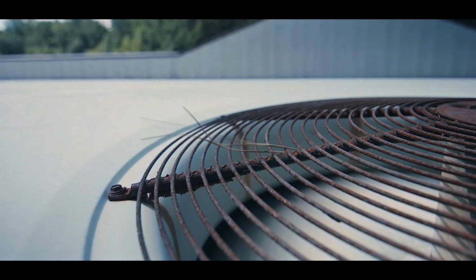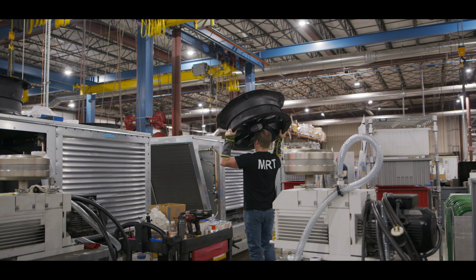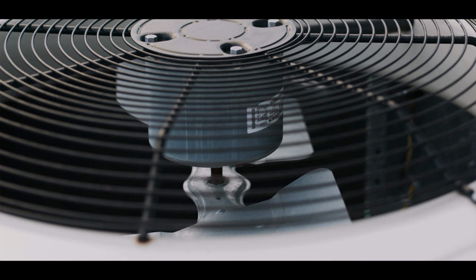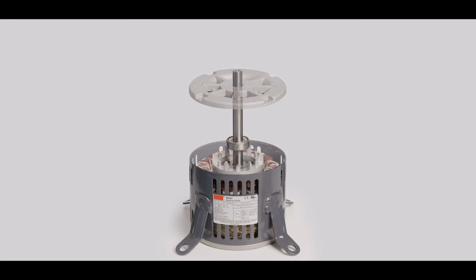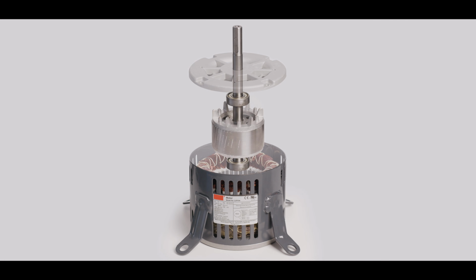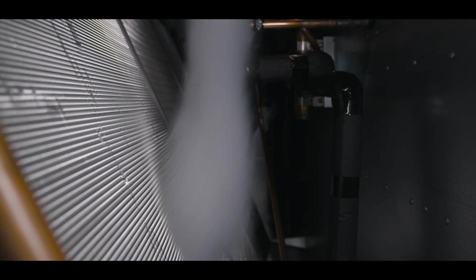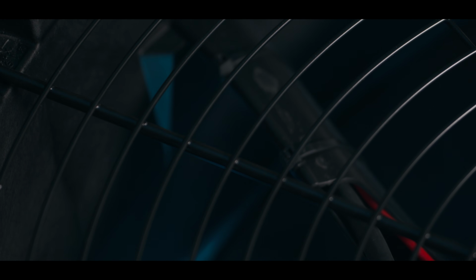There were many examples during the design phase of, let's try this technology, or let's try that and see if it works. Some of those were just complete dead ends. We realized that right off the bat. For example, on our outdoor condensing fans, we tried to use an industry standard prop fan with a small motor. And we realized really quickly, with a high quality, high performance unit, the condensing coils end up having a little higher static pressure. What we found is those prop fans could not pull the air through those coils correctly, and basically led to higher operating pressures, which translated into higher energy use.